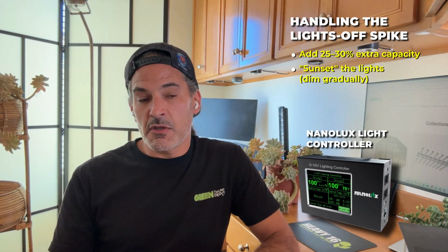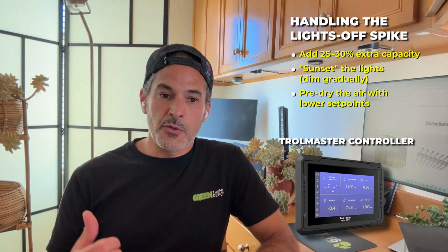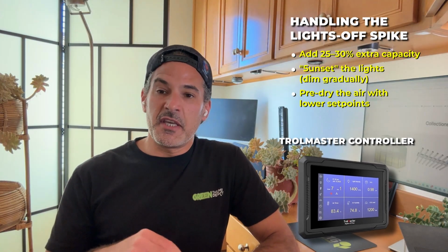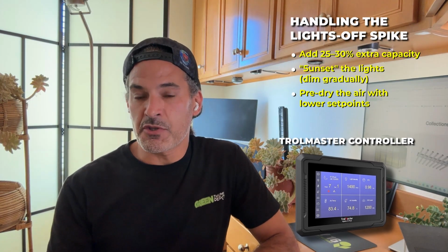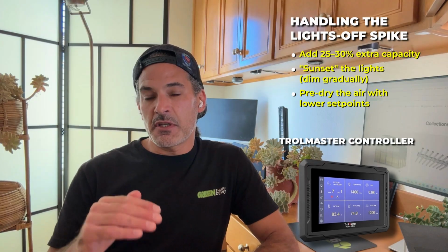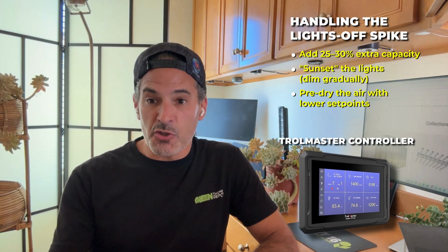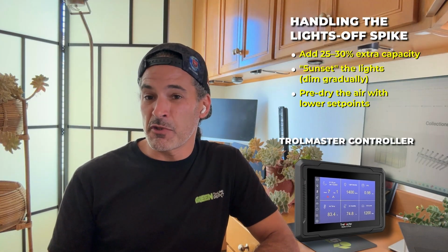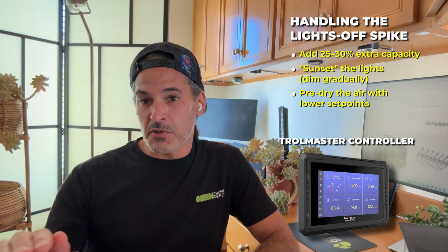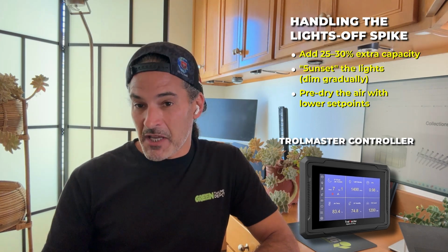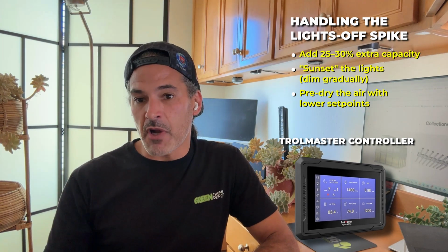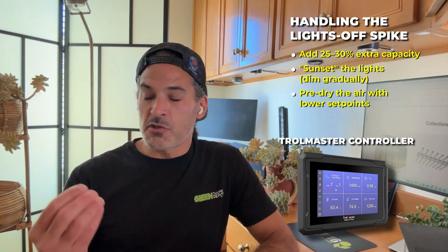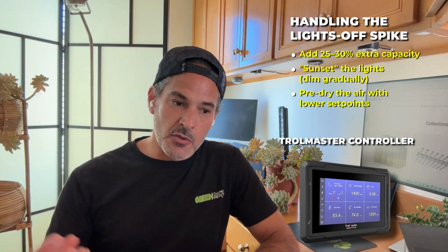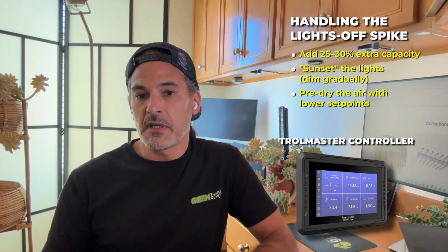The other thing you can do is program your dehumidifiers to begin removing more moisture. You can take the set points and set them such that they are trying to dry out the air more than you really want as you approach lights off, so that when the lights do go off, you're starting from a drier baseline and there's less moisture in the air. So as it cools, there's less moisture to potentially precipitate out.